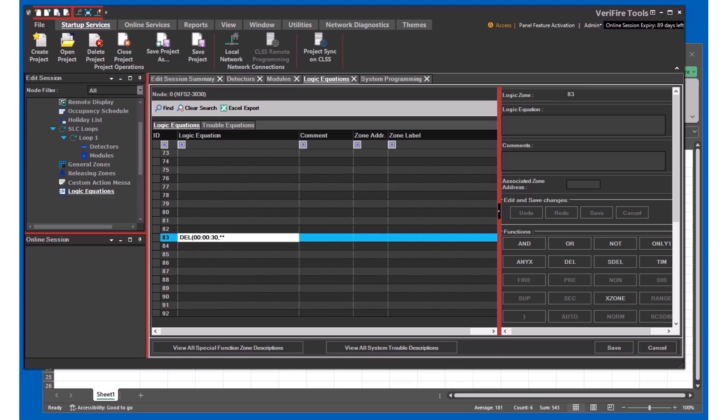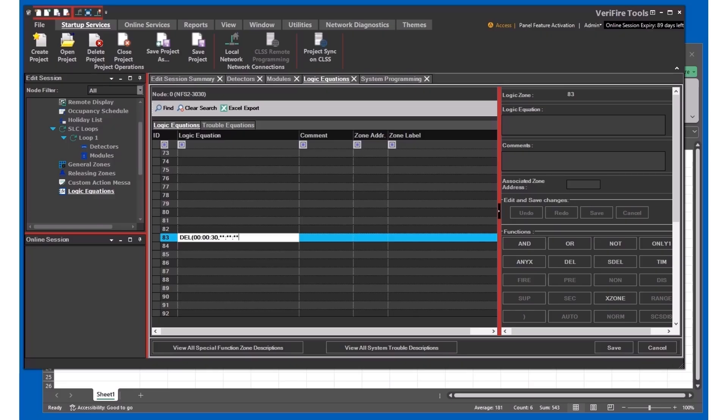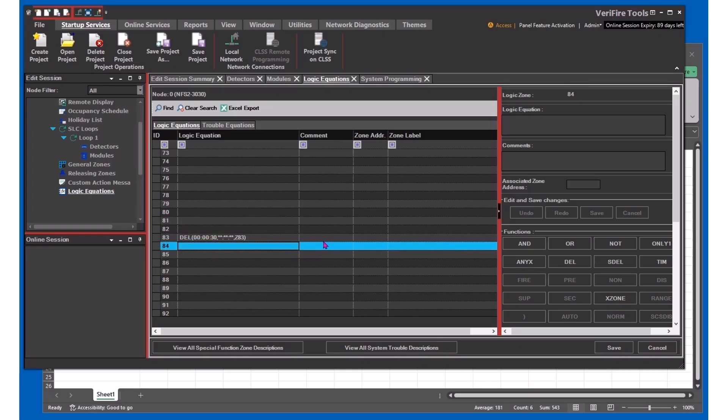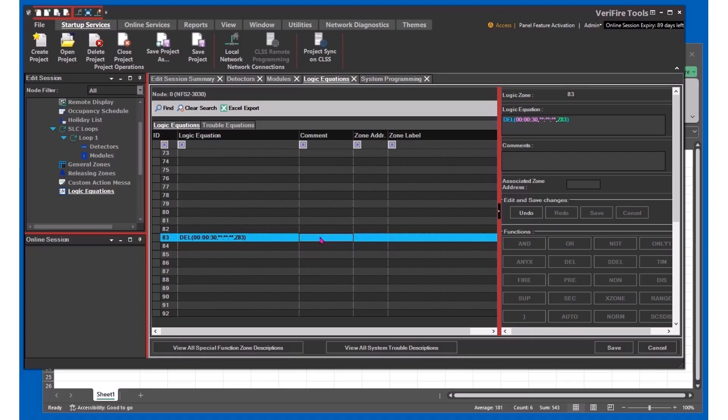The second part of the timing here is how long you want the relay to stay on. If you want it to stay on indefinitely, you just put it all wildcard stars. And then we're going to apply this to input zone 83, and we'll label this as shunt delay, and then we should be good to go.